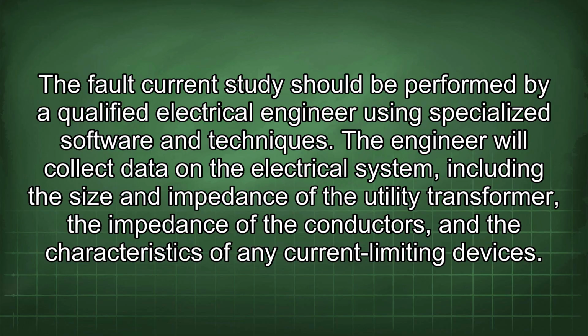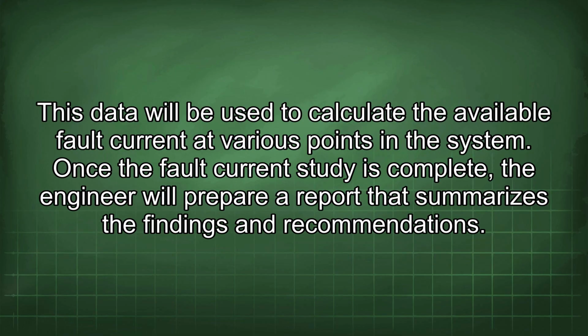The fault current study should be performed by a qualified electrical engineer using specialized software and techniques. The engineer will collect data on the electrical system, including the size and impedance of the utility transformer, the impedance of the conductors, and the characteristics of any current limiting devices. This data will be used to calculate the available fault current at various points in the system.